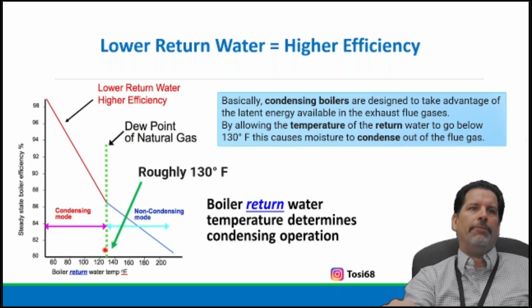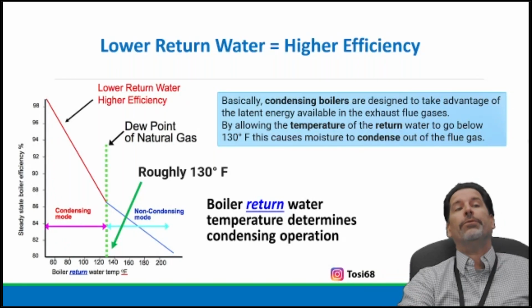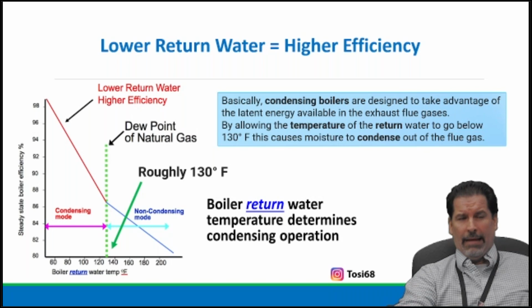right here's 130, roughly 130. Go to the left, where let's call it 87% efficient, steady state efficiency. The boiler is running steady state at 87% with return water from the system at 130. We don't start achieving what the label states until we literally have almost 80-degree water returning. So these charts, there's hope. I mean, wow. To say we want to go from 180 now to 100-degree supply water with a 20-degree split, and now having 80-degree water returning.